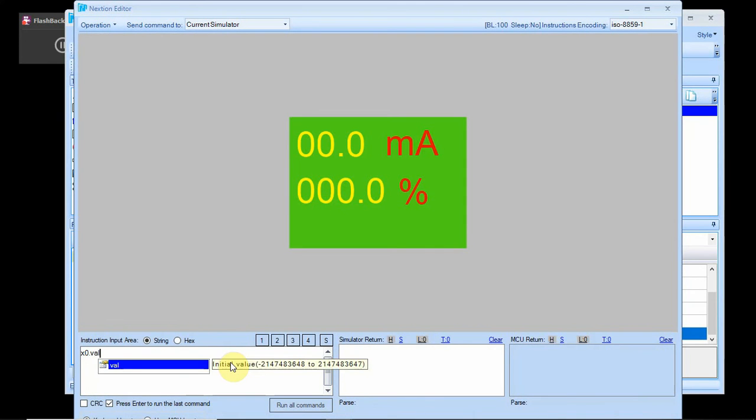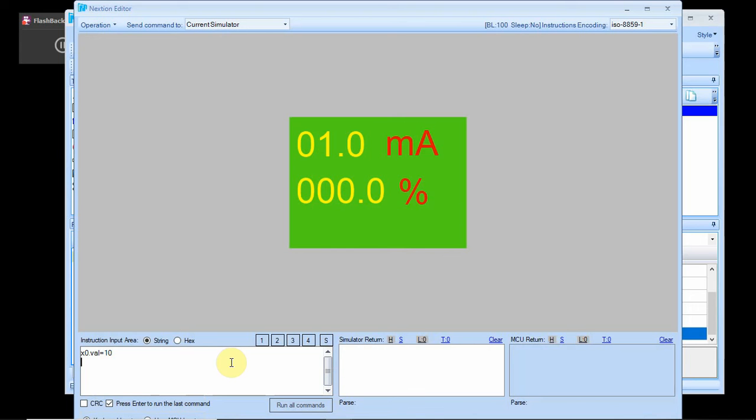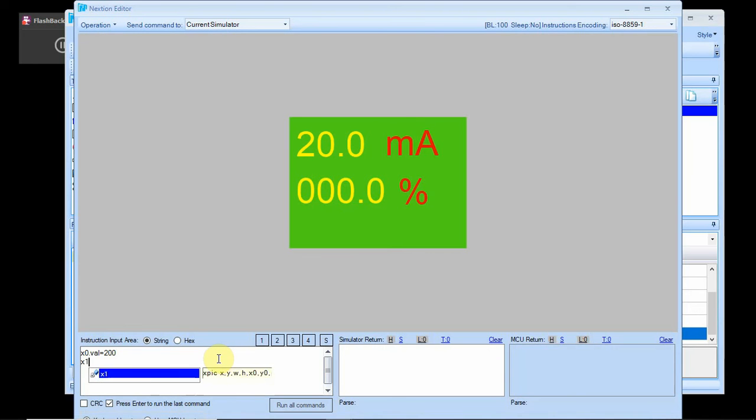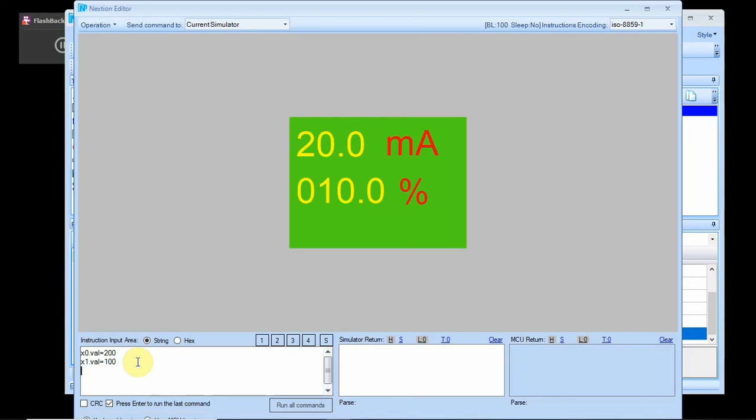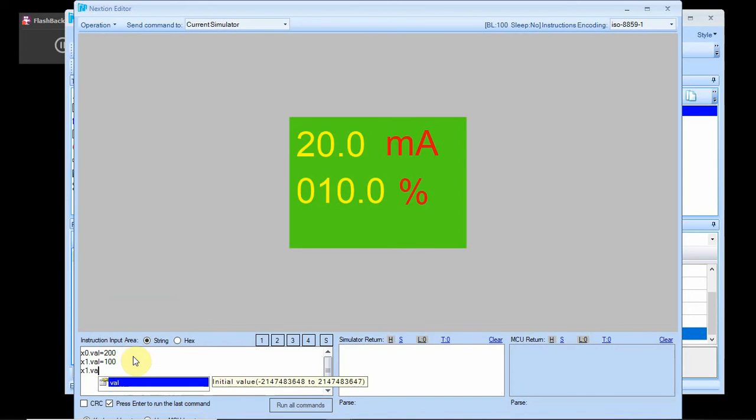One thing I can do before I do that, if I go to debug right here, I can say x0 dot val equals 10 just to see how it works. So the trick is that for four milliamps you have to send it a value of 40 because it just puts the decimal point where it should be. So four milliamps is a 40. It's kind of a trick. I kind of wish I could hide that leading zero but there may be a setting for that. So 20 milliamps is a 200. Let's try x1 dot val, the minus 25.